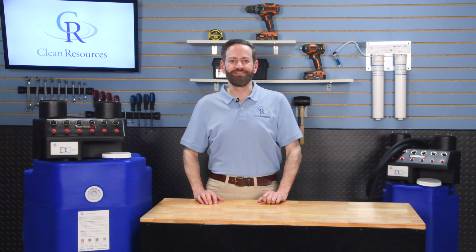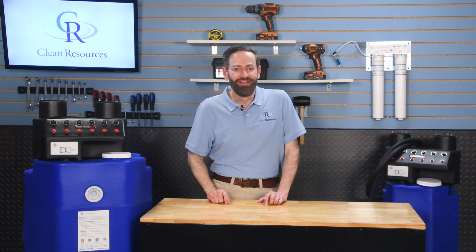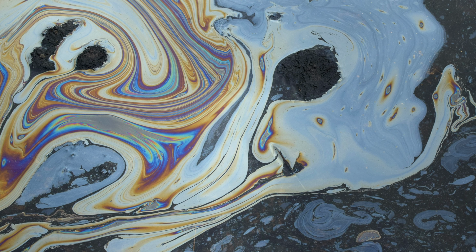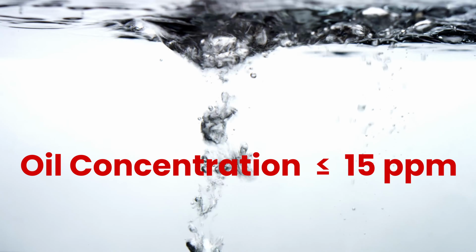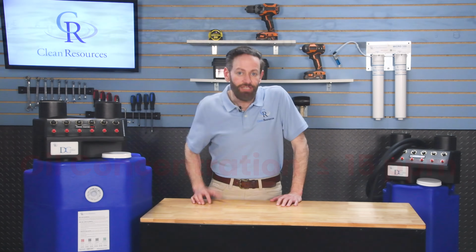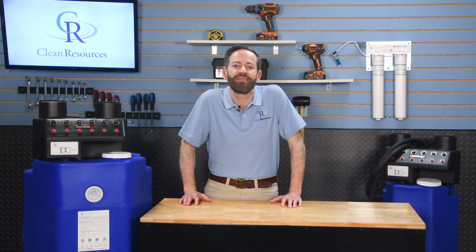My compressor condensate looks clear, so it's probably fine, right? Wrong. Most lubricants are not visible in water unless concentrations are greater than 500 parts per million. State municipal regulations can require concentrations as low as 15 parts per million. You need an oil-water separator that can filter out that excess lubricant to stay in compliance.